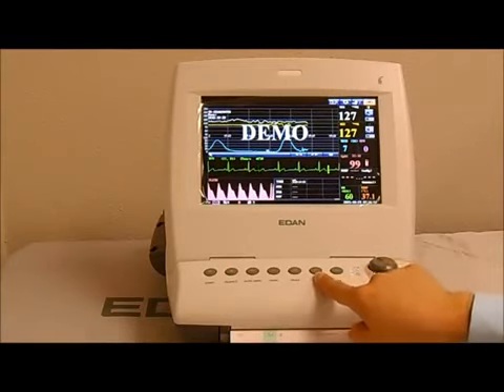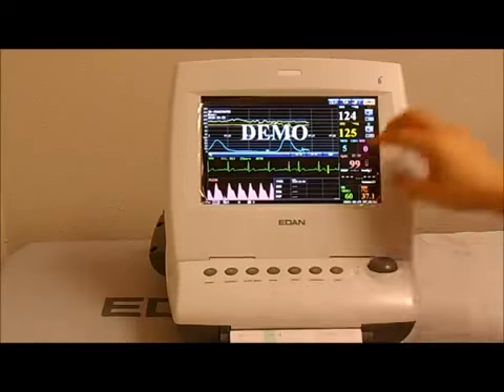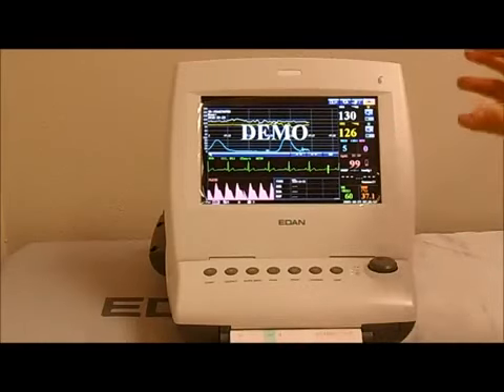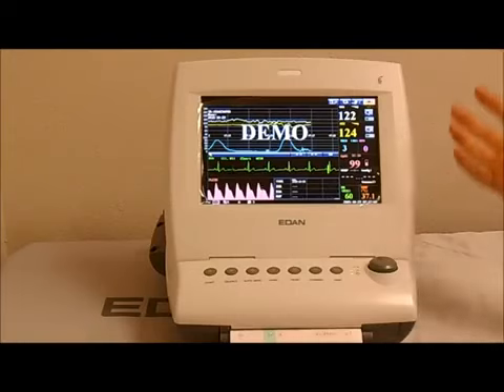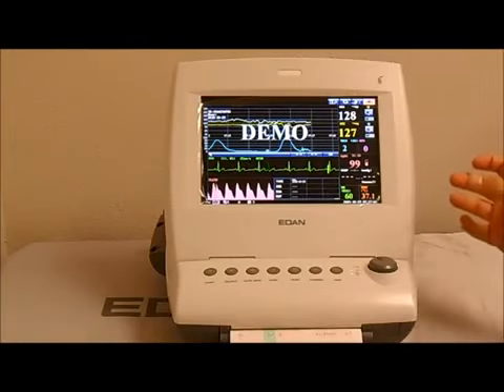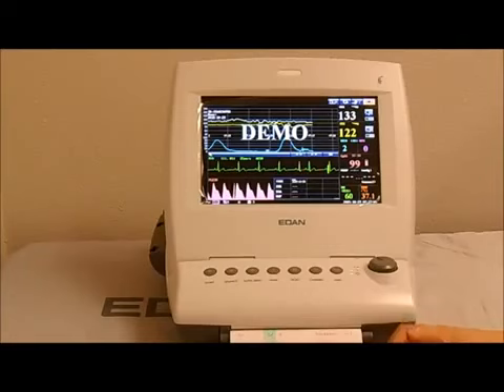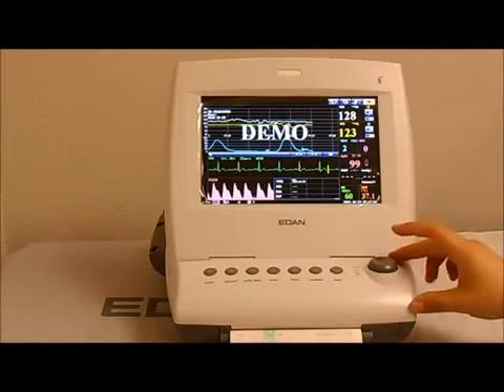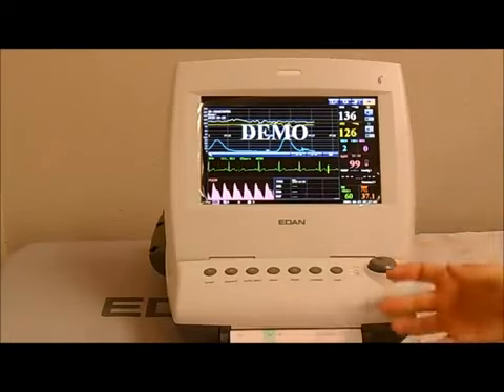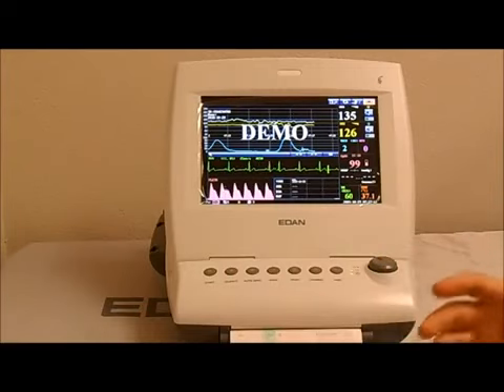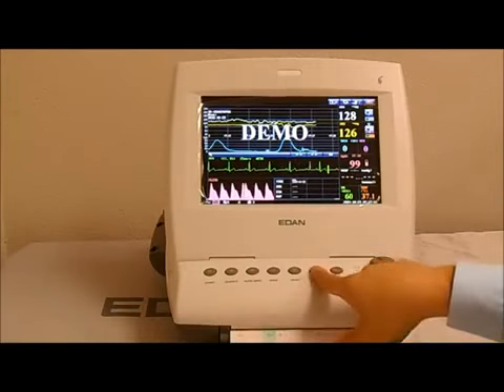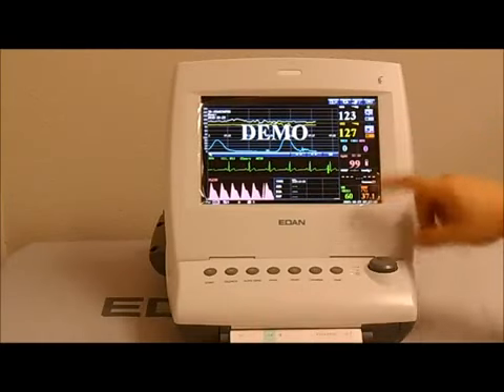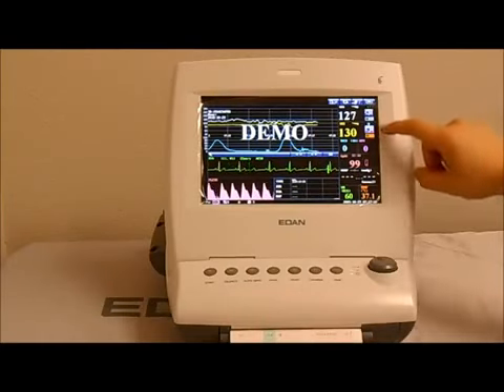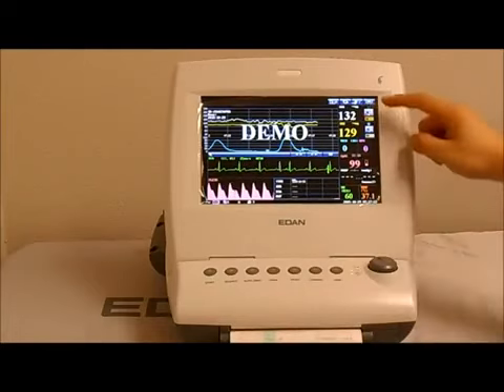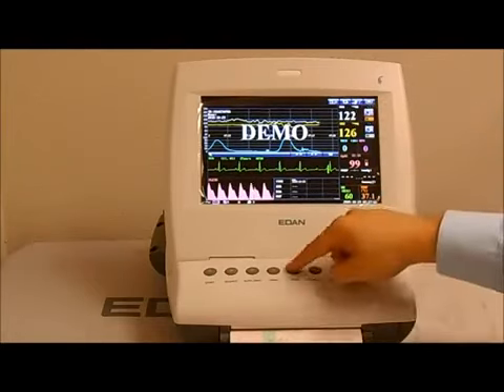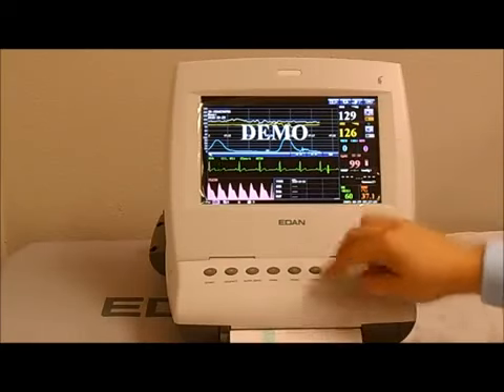Next we have the channel key. The monitor will give you FHR feedback, so it'll give you the sound of the FHR. If the patient has twins, you would have two FHR transducers on the patient at the same time, but the system can only give you the FHR sound of one transducer. Otherwise there's going to be overlapping sounds and it's going to be chaotic. So if you press the channel key, you go from the sound feedback of transducer 1 to transducer 2. So you go from FHR 1 to FHR 2. That's the channel key.